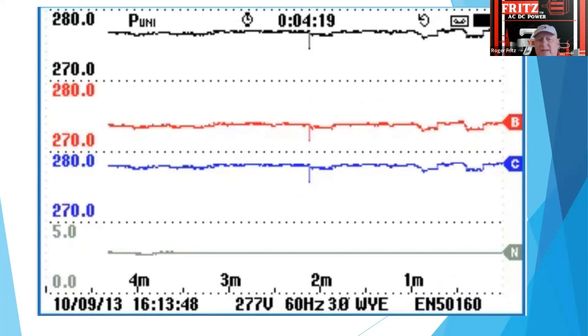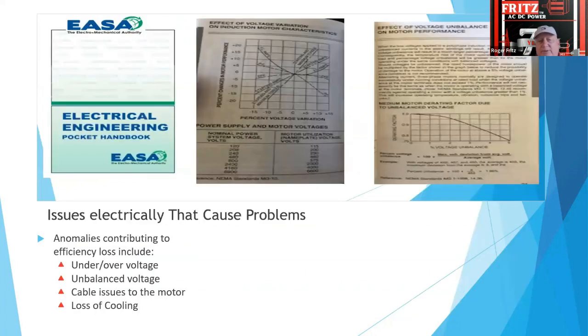Again, looking at those various input voltages. We also, from taking a few pre-readings, will give a recommendation of which VFD we should actually supply, because there are 480 volt inverters, but those are rated roughly plus or minus 15%. So you can see voltages up as high as 510, 520, but there's application in some of these older mills, especially up in New England or down in the Carolinas, where a lot of the motors are even still running on 575 volt, where you go up to Canada. So you want to get the right input voltages set up on the drive controls, and we tend to ask a lot of questions when people are looking into it. Again, the cause factors that are out there: under voltage, imbalance, cabling issues to the motor.